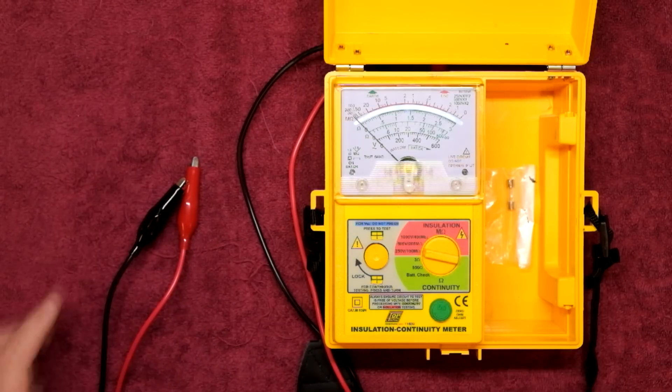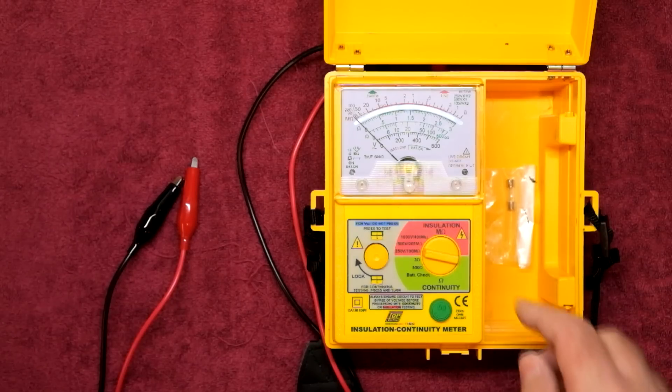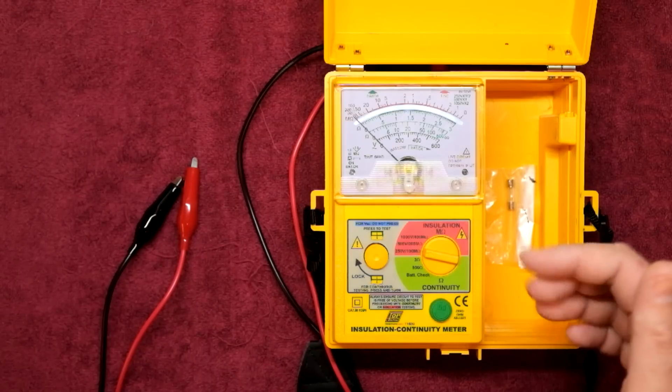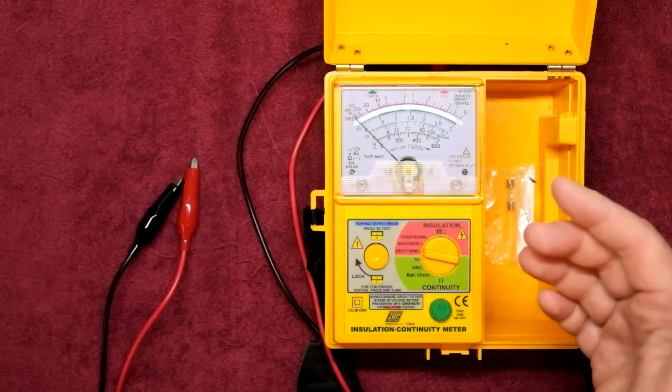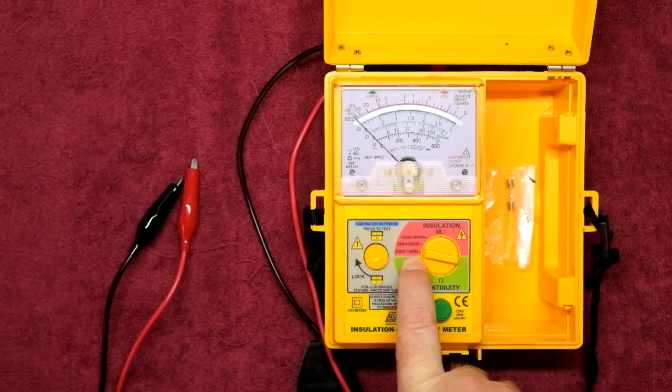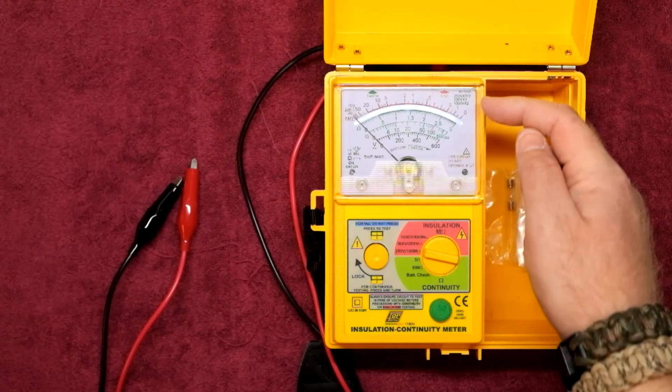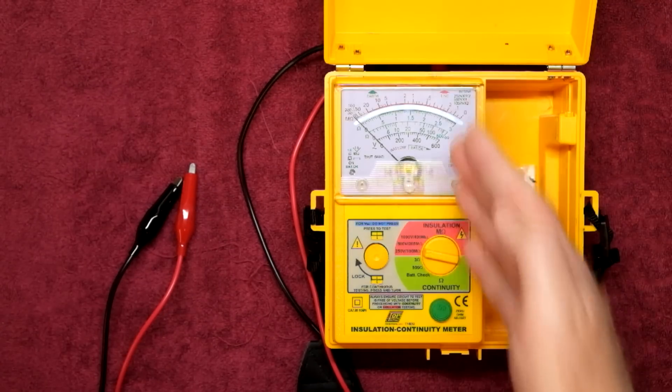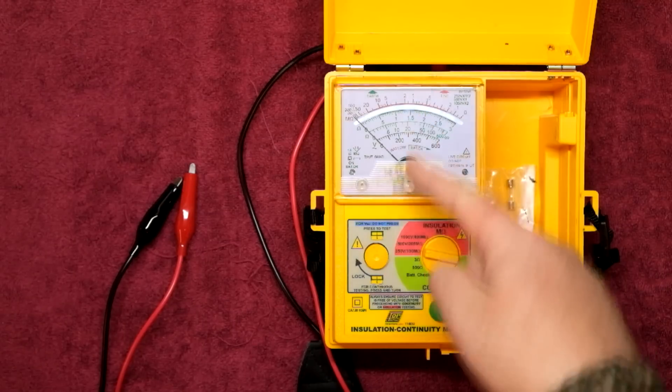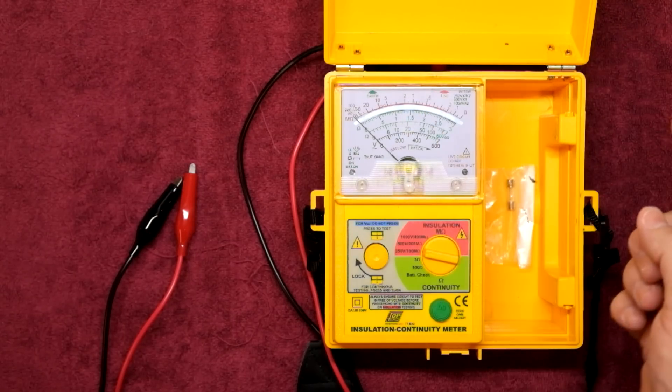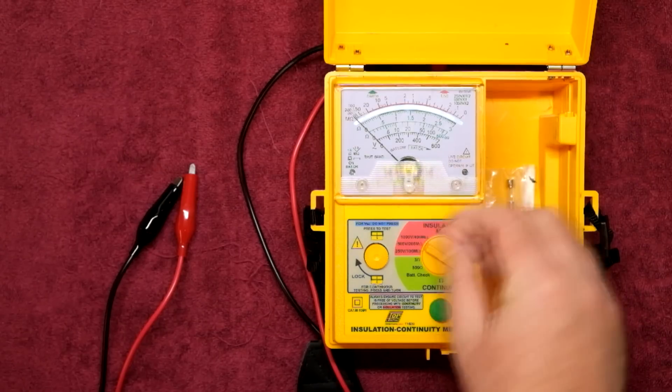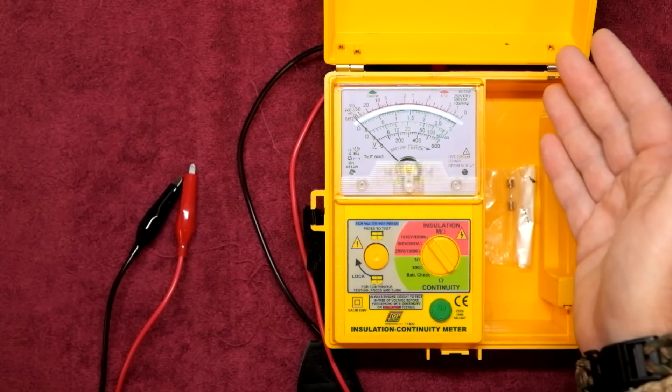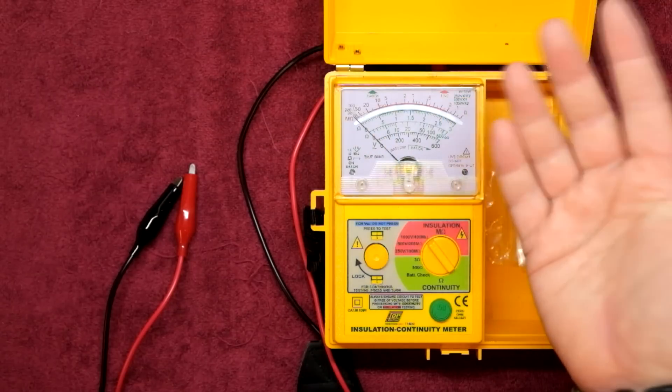But where this thing really comes into its own is the insulation resistance tests. This specific meter will do 250 volts, 500 volts or 1000 volts. The readings obviously change accordingly. For example if you're on the 250 volts you'll see it says 100 mega ohms. So basically at 250 volts you're halving whatever the displayed resistance is. So for example if you read 2 mega ohms when you push the test button you halve it so it's actually 1 mega ohms. If you set it on the 500 volt scale it's exactly as it is. So whatever it reads that's currently what it is and if you go to the 1000 volt scale you multiply it by 2. So if you read 1 it's now 2 and so on so forth.